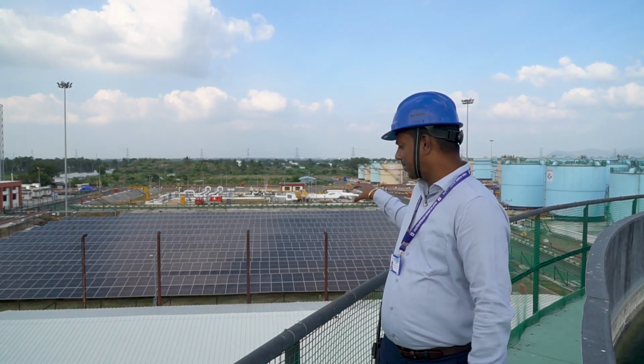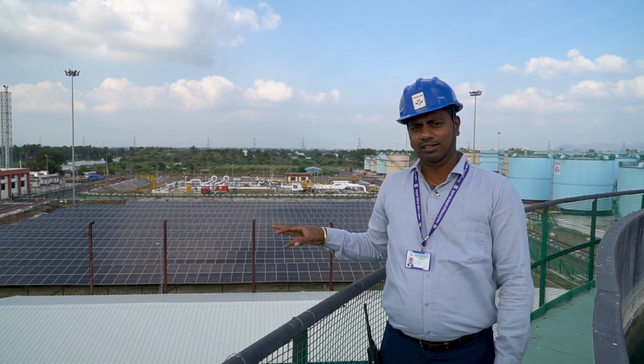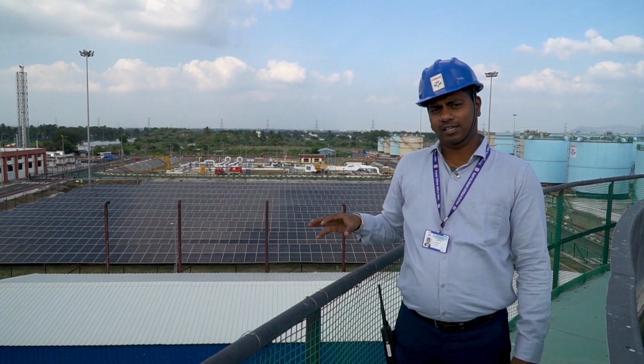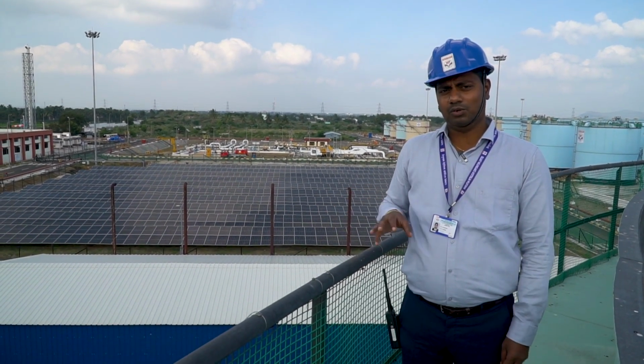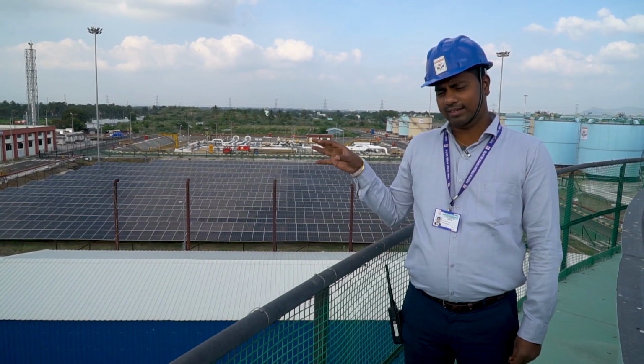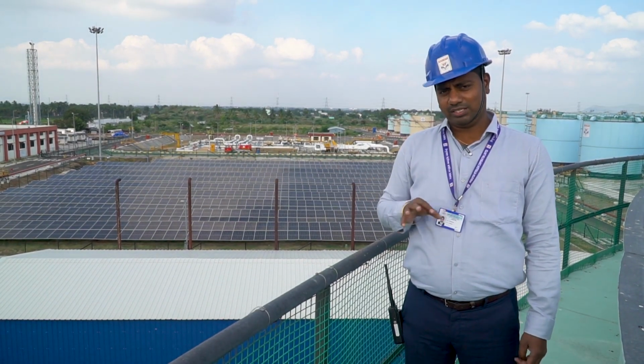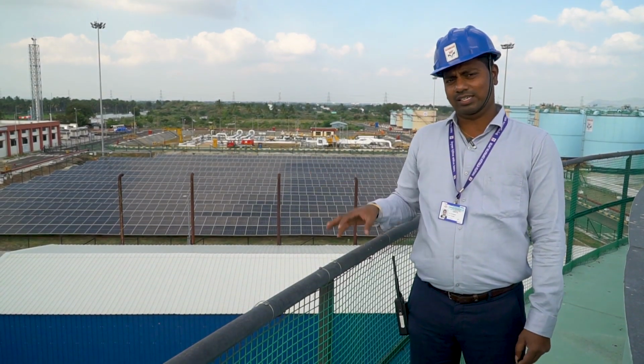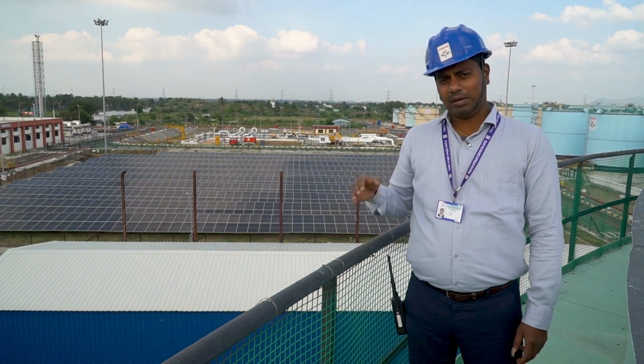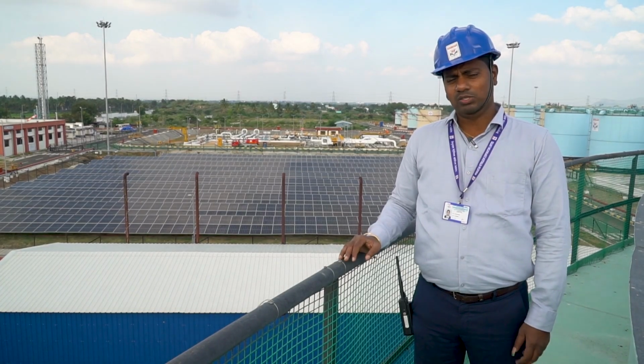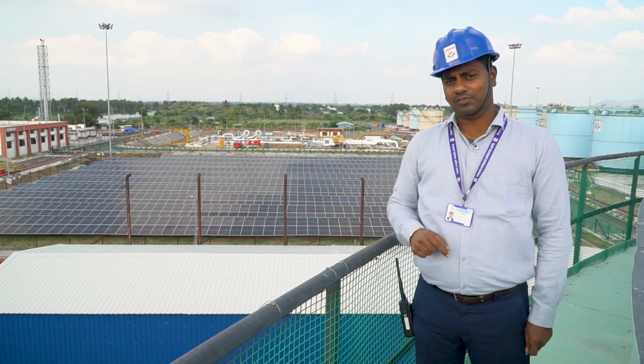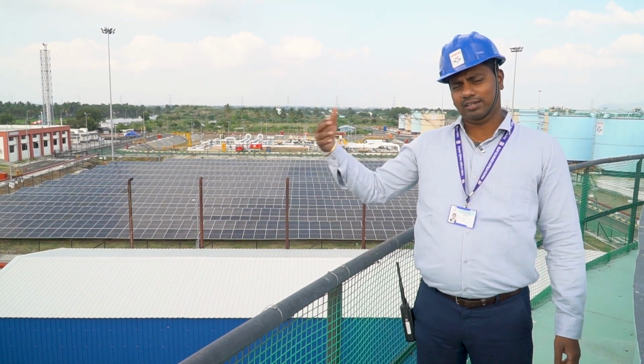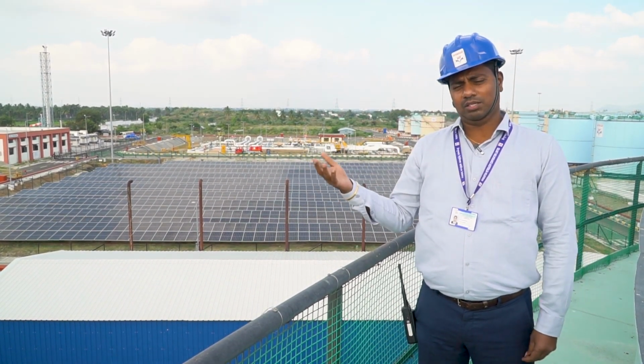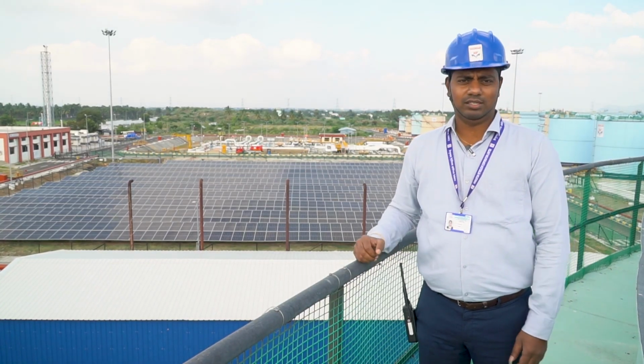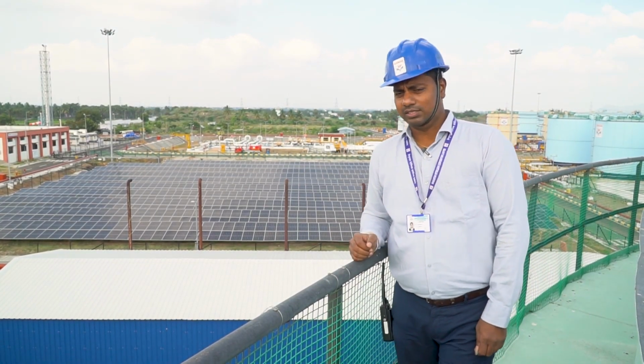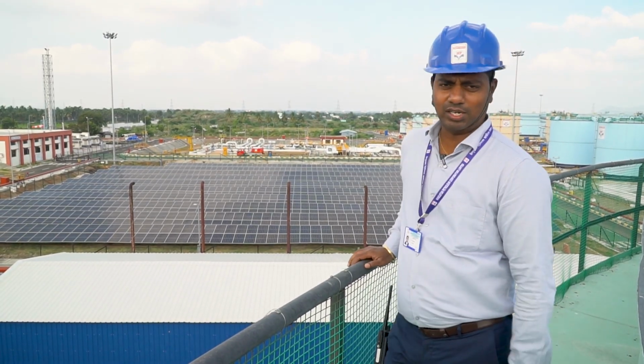You can see solar panels installed in this terminal, which cater to around 550 kWp. That is approximately 70% of this terminal's power consumption taken care of by solar. Here we have bi-directional meters installed, so that excess production from the solar is fed to the grid, and the grid will pay for it. So these are our 550 kW solar panels.